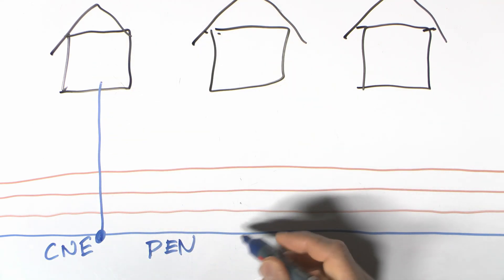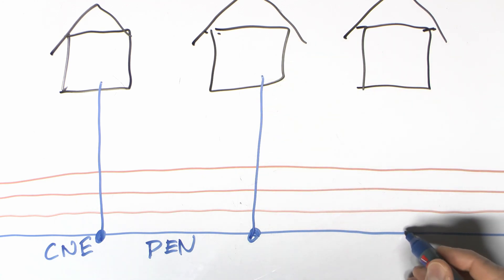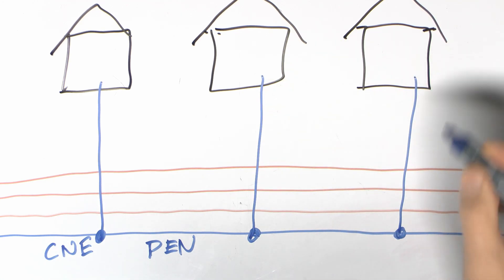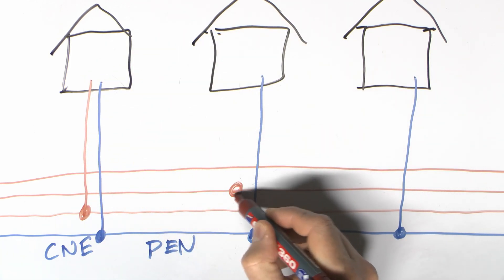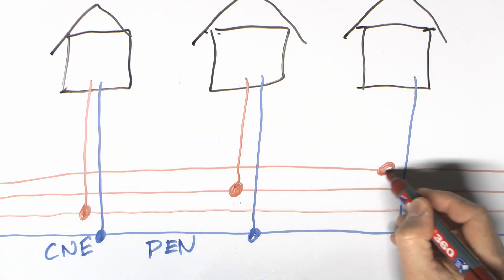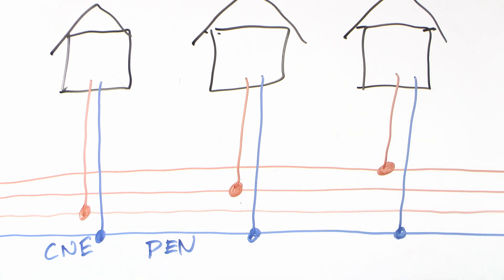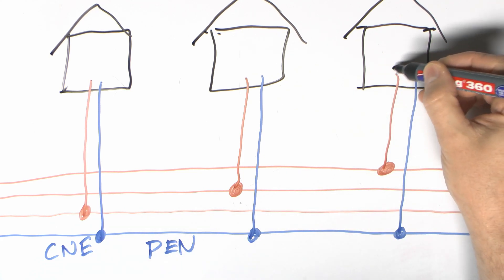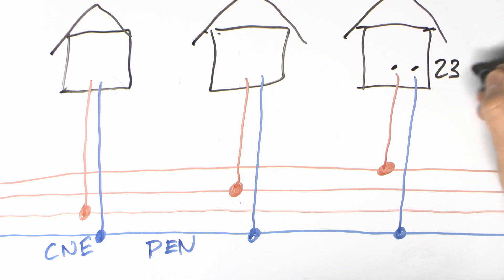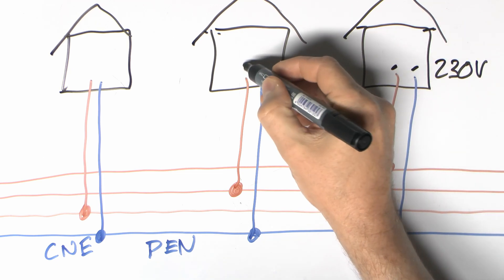The CNE conductor will be tapped off into all of the properties of course, so you're going to have one going over there, one here, and one there. And then the other conductor in the cable, there'll only be one. As I say, most properties in Britain only have a single-phase supply. Not unheard of to have a three-phase in a domestic property, but it's certainly an unusual situation. And you're going to have one of them coming off here. The next house may well have the other conductor there, and then the third one will have that one.